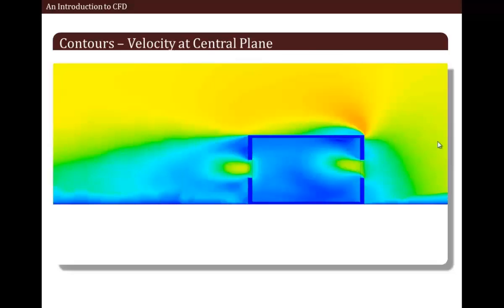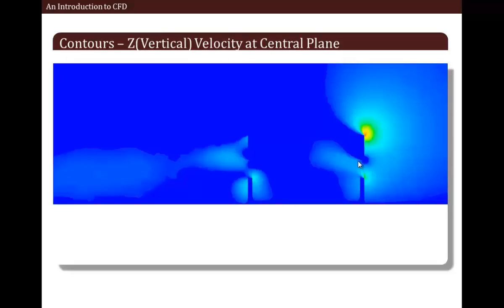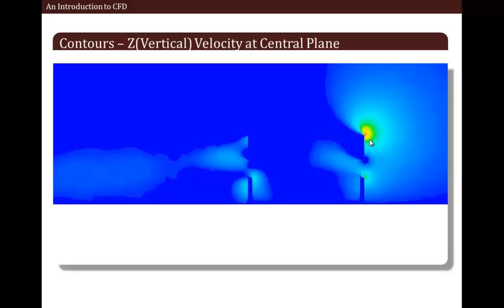Now let us watch the contours of velocity, again at the central plane. We can see the velocity decreasing as we approach the room, with high velocities at the windows. Now we are looking at the Z velocity — that is the vertical velocity — at the central plane. Areas not colored with dark blue have velocities in the positive vertical direction, meaning air is going up in those places. Once air enters the room from the window, it tends to rise up due to natural convection. The yellow colored zone is basically the flow path which tends to rise above the room while passing over it.